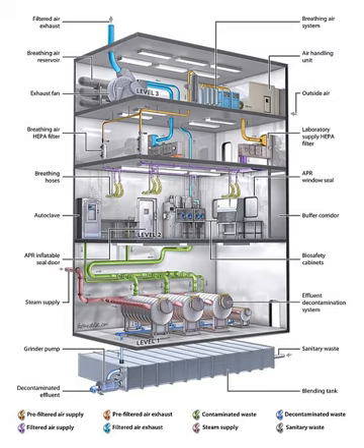Biosafety level 4 is the highest level of biosafety precautions, and is appropriate for work with agents that could easily be aerosol transmitted within the laboratory and cause severe to fatal disease in humans for which there are no available vaccines or treatments. BSL-4 laboratories are generally set up to be either cabinet laboratories or protective suit laboratories. In cabinet laboratories, all work must be done within a class 3 biosafety cabinet. Materials leaving the cabinet must be decontaminated by passing through an autoclave or a tank of disinfectant. The cabinets themselves are required to have seamless edges to allow for easy cleaning. Additionally, the cabinet and all materials within must be free of sharp edges in order to reduce the risk of damage to the gloves.